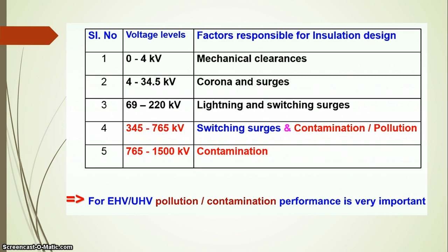For 345 to 765 kV, the extra high voltage level, switching surge testing is very important as voltage levels increase. Additionally, contamination and pollution become a critical factor — when an insulator gets polluted due to bird droppings, burning of agricultural waste, or dust, a layer forms on the insulator surface causing partial arcs and scintillations that can develop into a complete flashover of the insulator string.